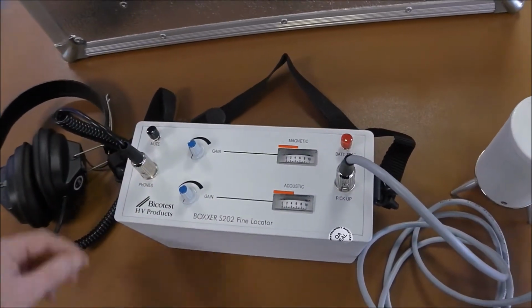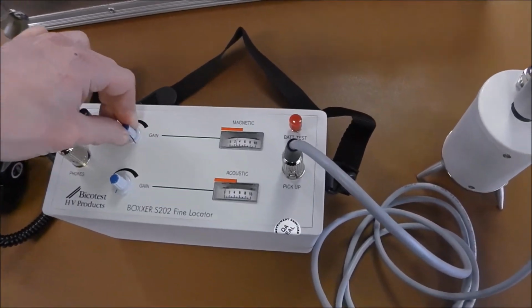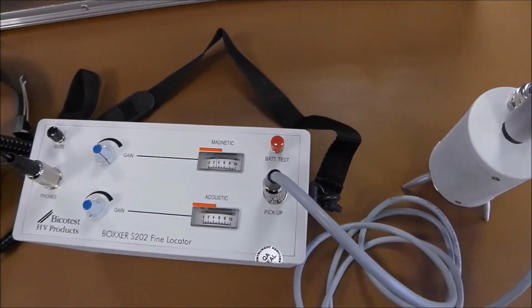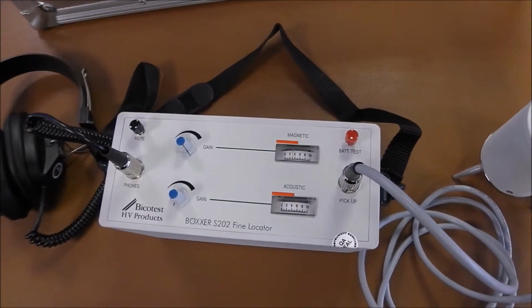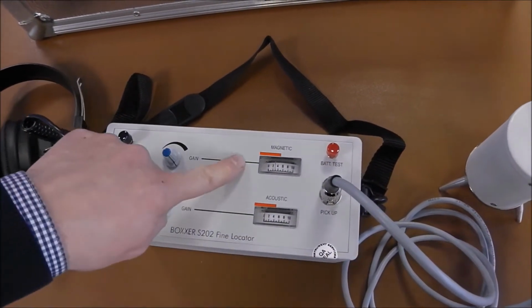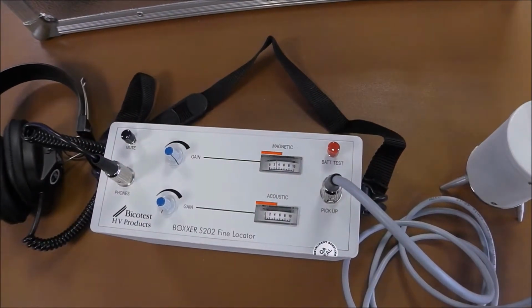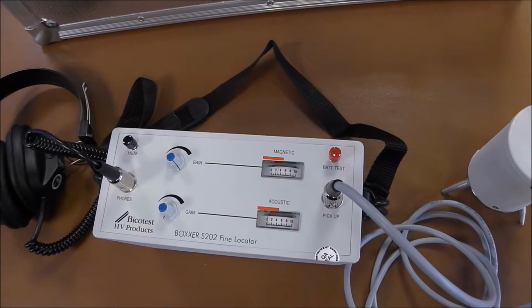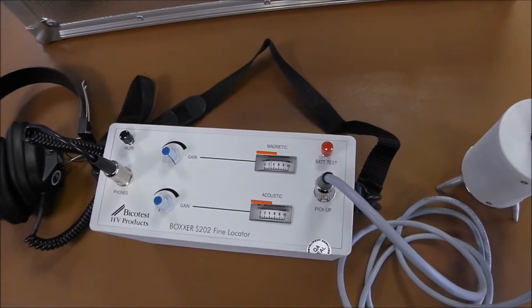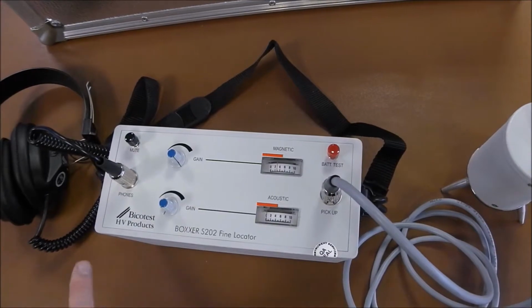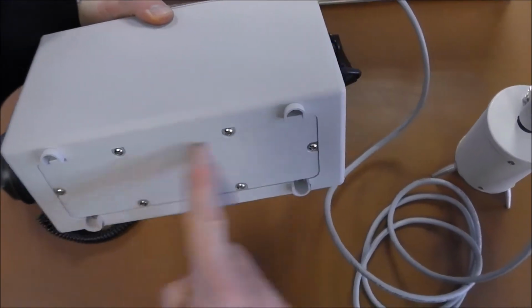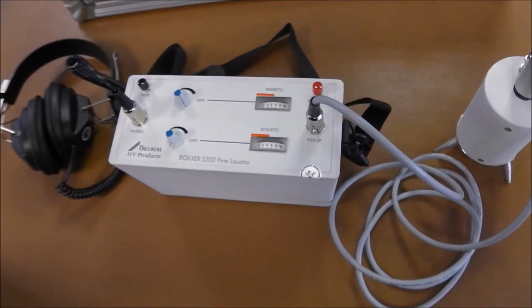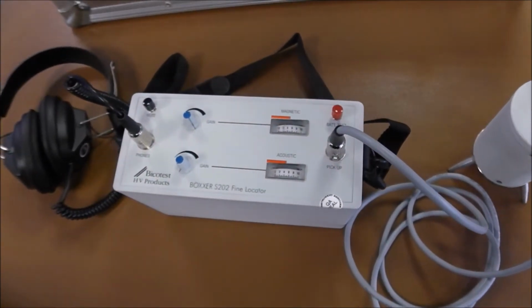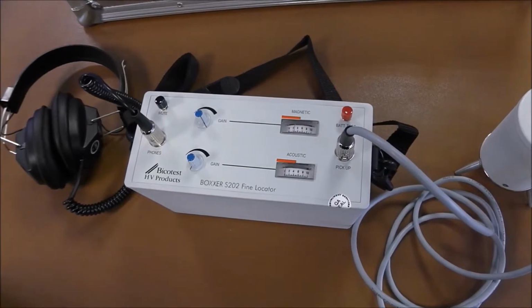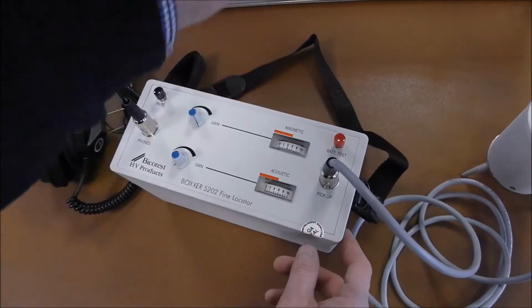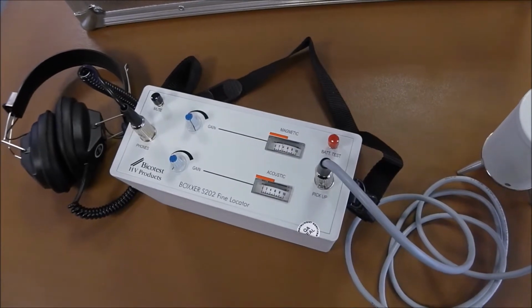Rotate the magnetic channel gain control clockwise to its maximum position. The magnetic detector will now be in its most sensitive condition to pick up the magnetic signals from a pulsed cable. The control may be left in this position until signals are picked up from the cable under test, and may be then adjusted until an adequate deflection is obtained on the magnetic channel meter. Note that the magnetic detector is mounted longitudinally within the base of the amplifier housing. The optimum position, therefore, for maximum signal detection is when the amplifier unit is horizontal, directly above the cable, and orientated so that its length is at right angles to the cable route.